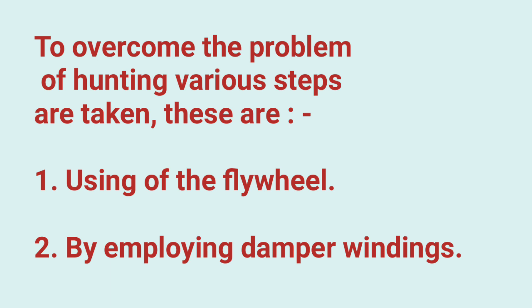Various steps are taken to overcome the problem of hunting. By using a flywheel, we can reduce or overcome the problem of hunting. And by employing damper windings, we can also reduce the hunting. Basically, damper windings are the main equipment which are widely used to overcome the problem of hunting.